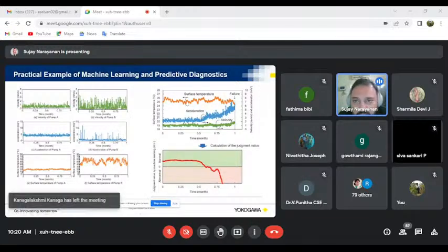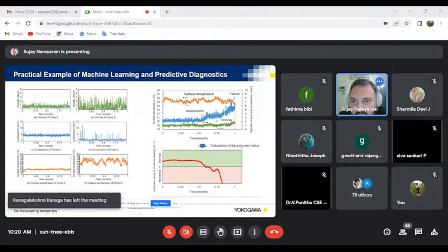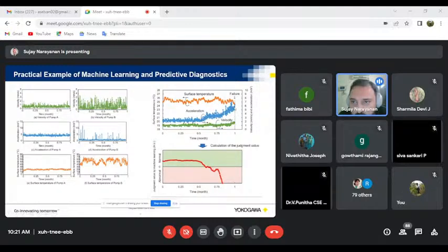So now all these things are put together on a single chart, and you can see the vibration is increasing over a period of time, and so is the velocity. If it is going to reach a certain threshold over here, then we are going to say failure is imminent. So that's what the machine learning is, a smart piece of software running behind and analyzing the data dynamically and giving you the status of whether the pump is in the normal zone or in the abnormal zone.